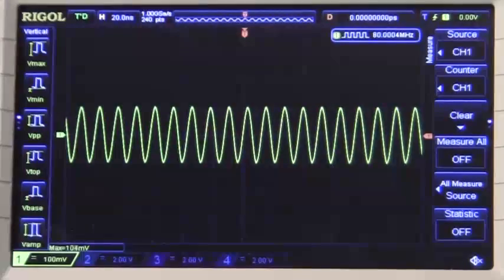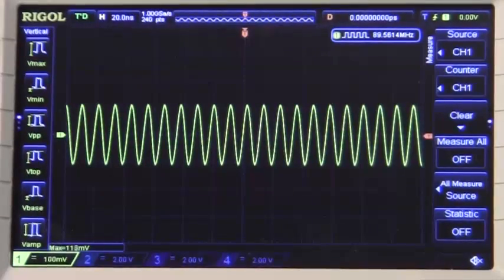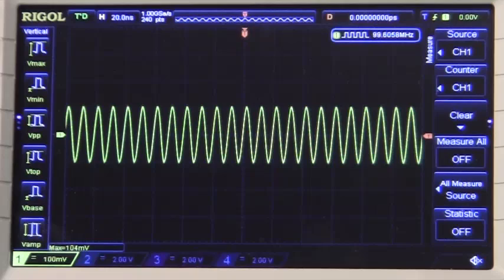We are at 104 mV at 90 MHz, then 112 mV. So it's spiking a little bit around there. At 100 MHz it's 104 mV. So now we've reached 100 MHz, which should be the bandwidth limit for this oscilloscope.